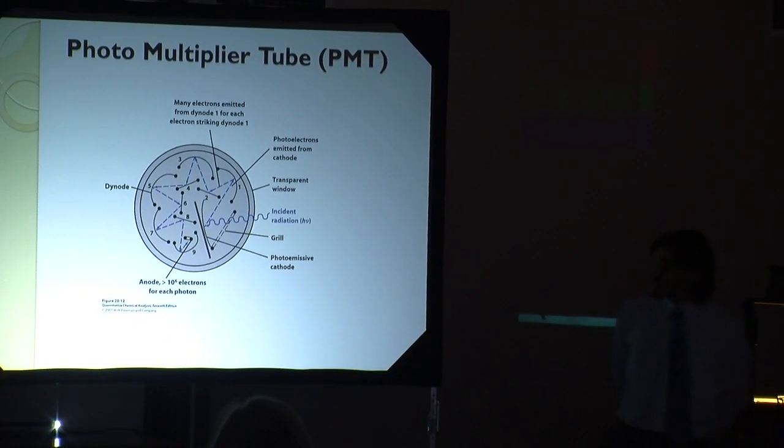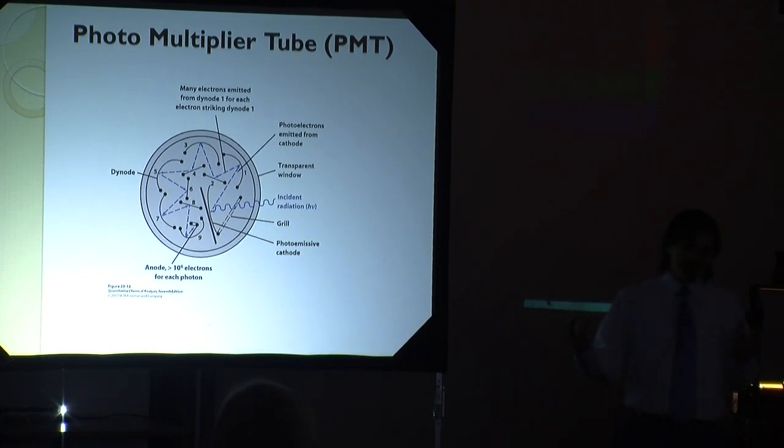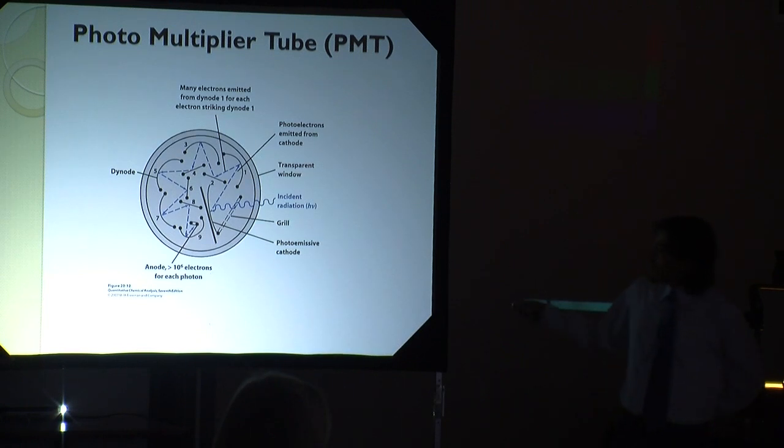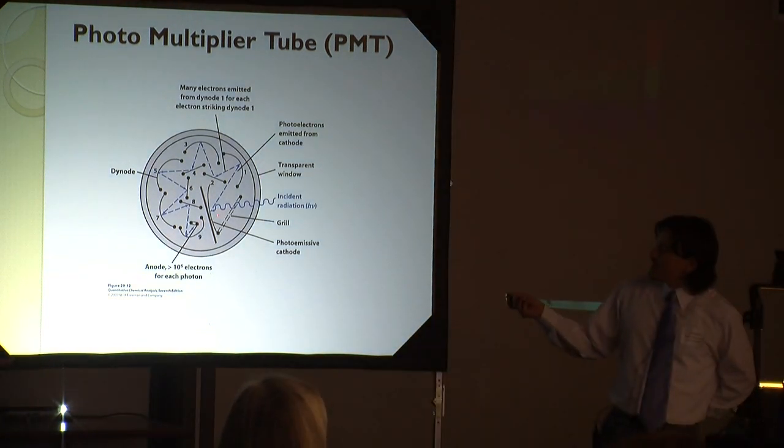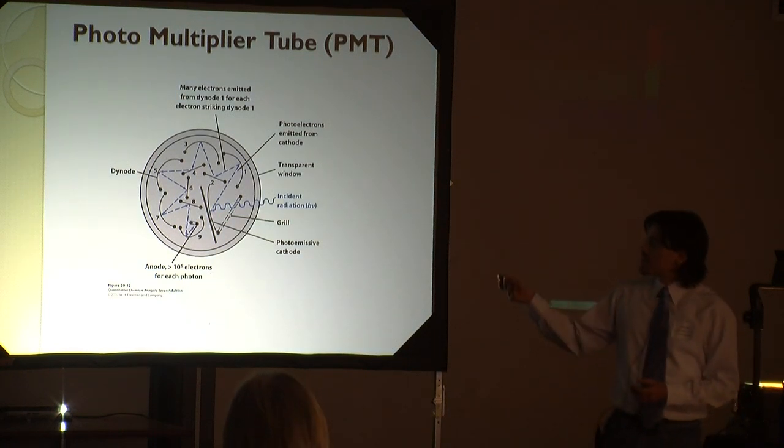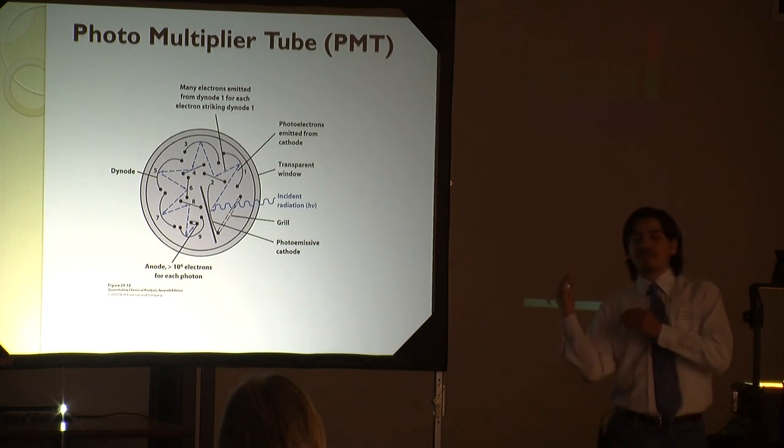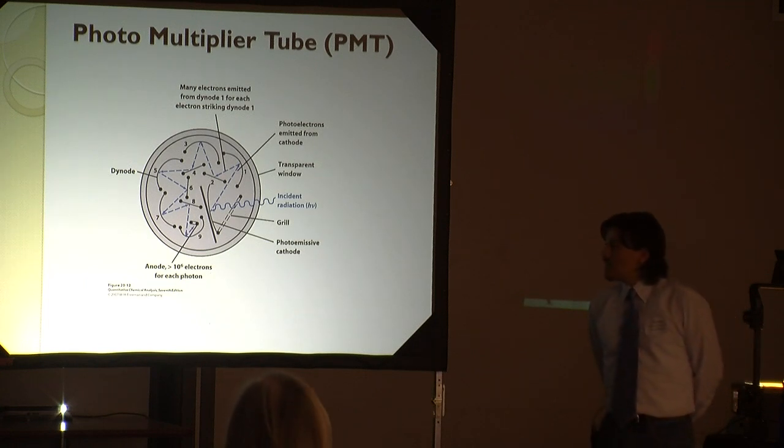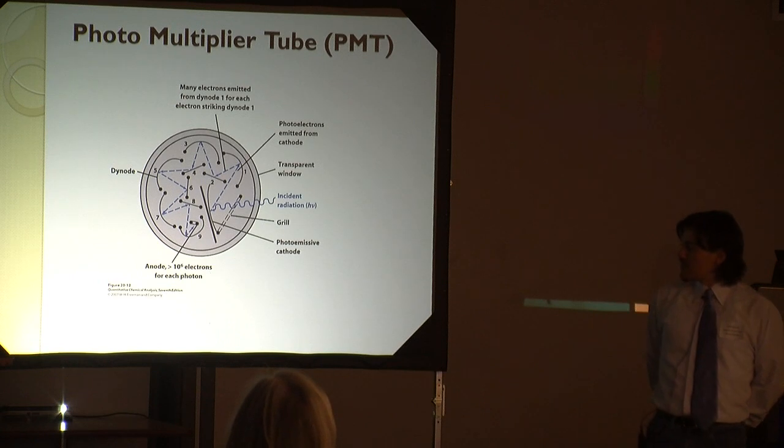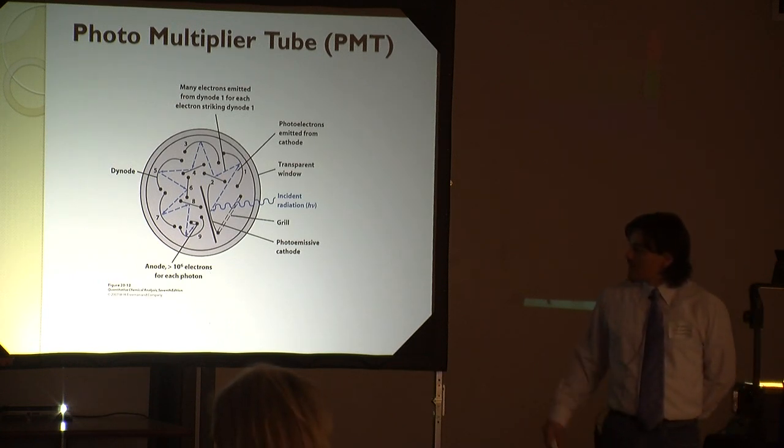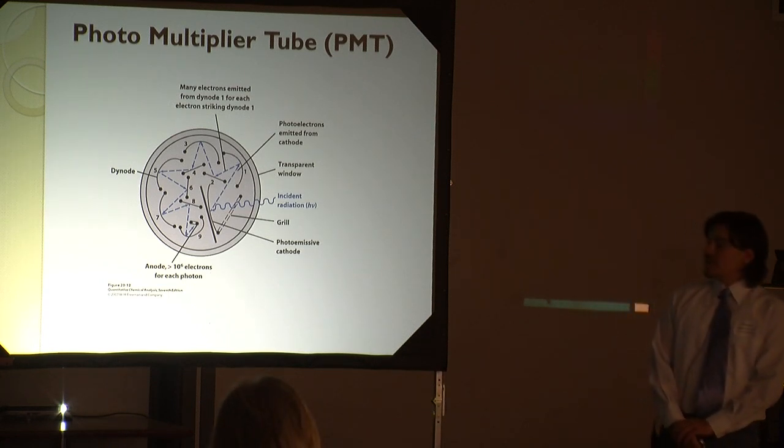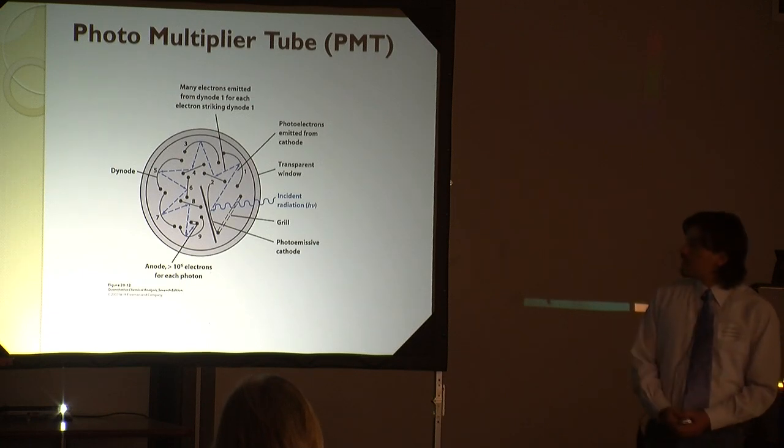As you see, there's nice light and before there was no light. That's what this instrument does. By measuring the degree of light that's coming out, we can detect exactly how much of the species of interest is in our sample. By doing this, we have a photomultiplier tube. If you think of a paper roll basically into a tube, we have one of the photons, the light beams emitted, and it strikes the tube. It excites an electron and ejects it from the tube's layering here. That electron contacts the tube again and it splits, and it ejects two electrons. That continues down for an exponential growth in the number of electrons at the end of the tube. By having this exponential growth, we can measure the difference of electric potential, and that gives us our detection and tells us exactly how much of the sample is in our unknown.